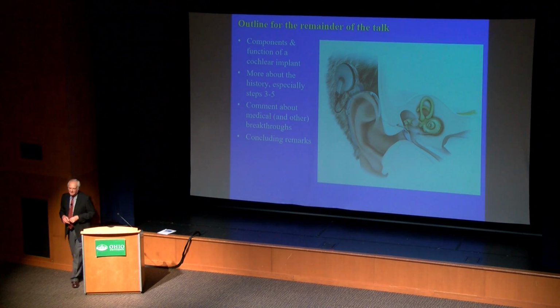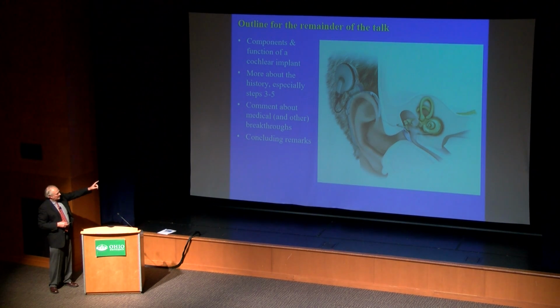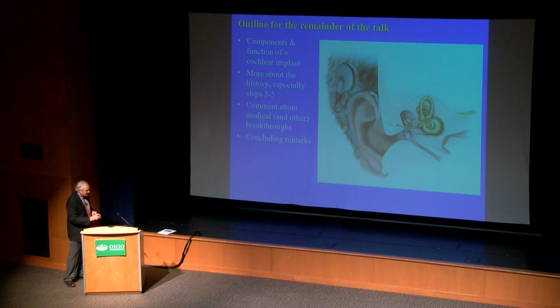So I've already described the external components of the cochlear implant. You can see the transmitting coil atop the outer ear, and immediately above the outer ear, you can see the tube that leads to the microphone input, the sound processor system just behind that, and the battery pack is behind the outer ear. Underneath the external transmitting coil is an implanted receiving coil, and you can see that in the light shading underneath that external transmitting coil. And across that closed skin barrier, information about the stimuli to be delivered to the cochlear implant is transmitted, as well as power, as I also mentioned before. Now let's see if this works. Oh, good.